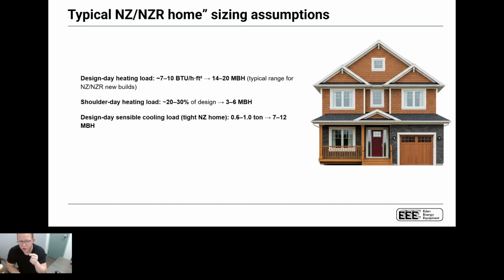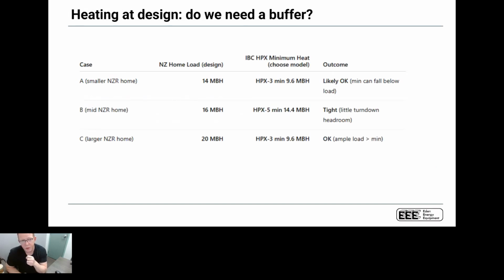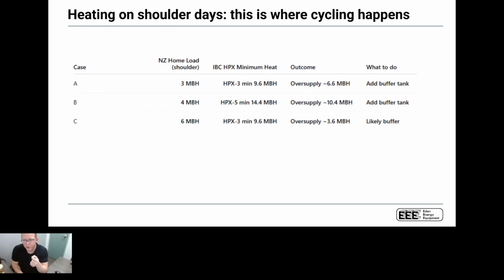And that's where it's really, really important that we pay attention to what's happening. So if we look at heating at design, and if you looked at an HPX3, which is a 3-ton, or an HPX5, I've put 3 scenarios up where I can make a really strong argument that I don't need a buffer tank. I can make this unit run at design, don't need a buffer tank. The challenge becomes that when I start to get into the shoulder days, we need a buffer tank, right? When you look at what does it mean when I only need 3,000 BTUs to heat that space? Well, the inverter drive can't get that low. The inverter drive is still trying to deliver 9,000 BTUs. So I need a buffer tank.